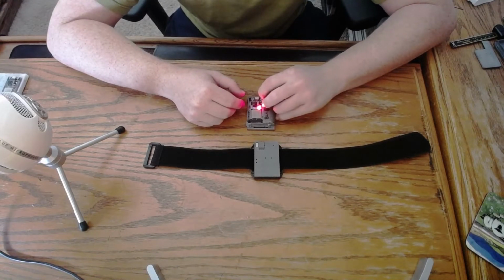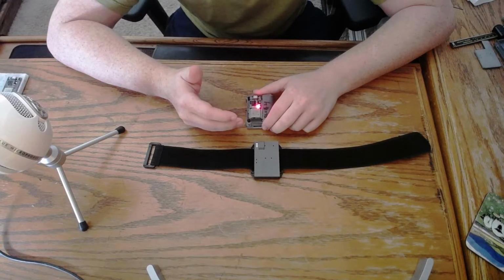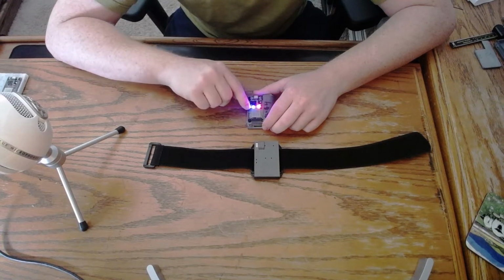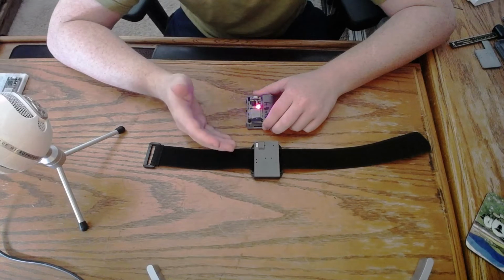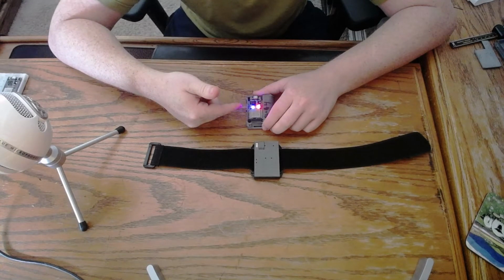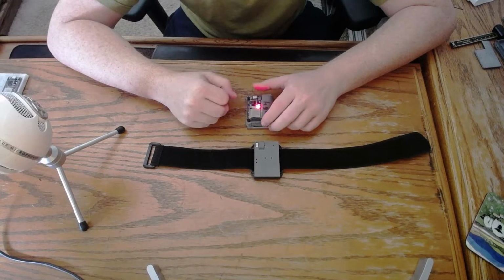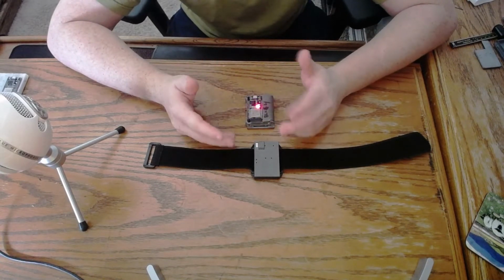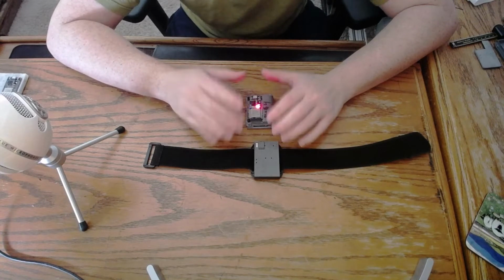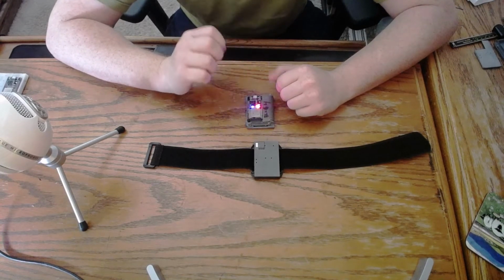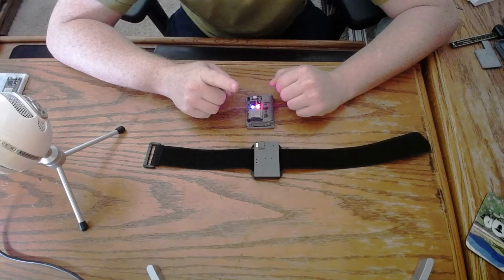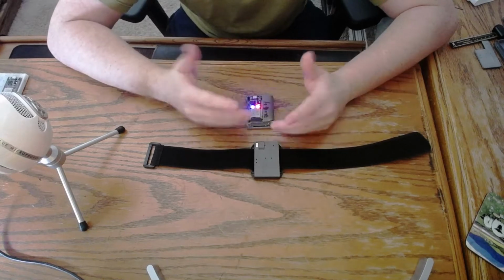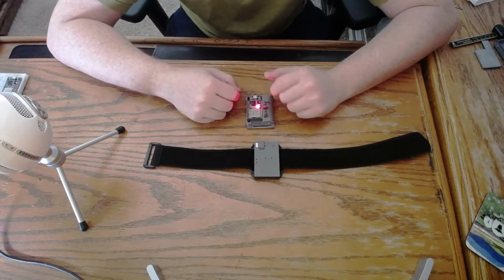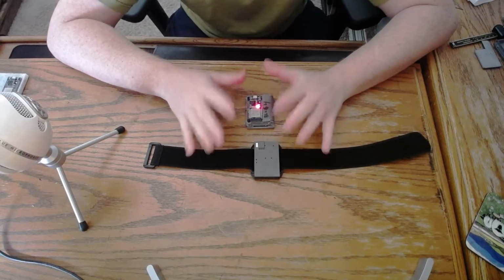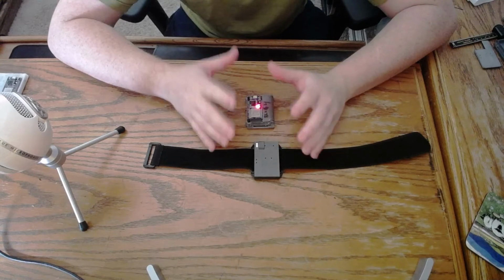So in this case, if I wanted to calibrate the accelerometer, I would hold for 1 second. Once I've held for 1 second and then release, it'll enter into the accelerometer calibration mode by blinking 4 times. This one doesn't have a time limit, so you can sit here as long as you want. But basically there's four different sensitivity settings. I only ever really use the first one, just because the first one is the most sensitive, but feel free to play around with the others. So to choose setting 1, I'll hold my finger there for 1 second. If I wanted to choose setting 4, I would hold it there for 4 seconds.